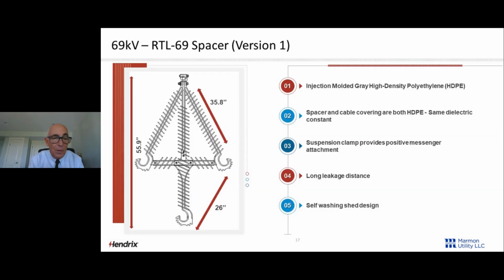Now, the one-piece spacer that you saw at the distribution voltages is gone. We can't make a one-piece spacer that's that big. So our first spacer was back when we were still using ring ties, back in the last century. It's made of high-density polyethylene, the same dielectric constant as the conductor. It's got a long leakage distance, and we use the same self-washing shed design.